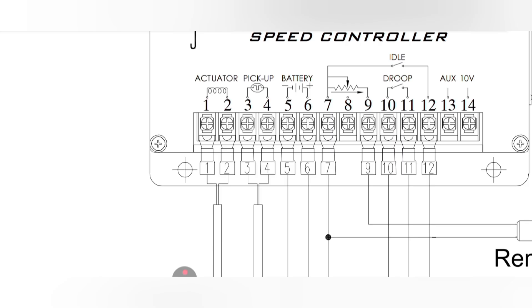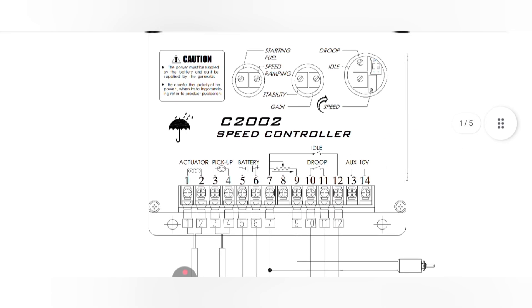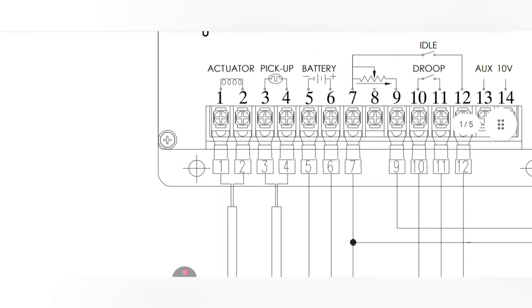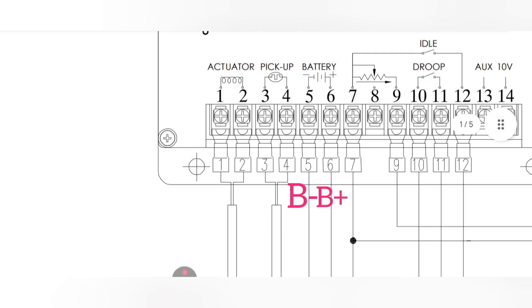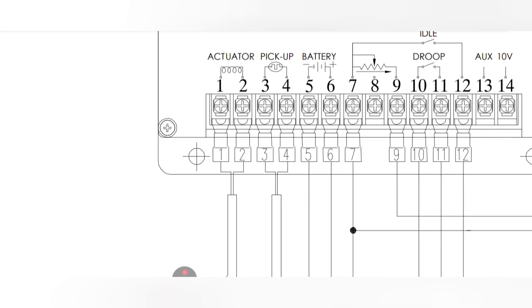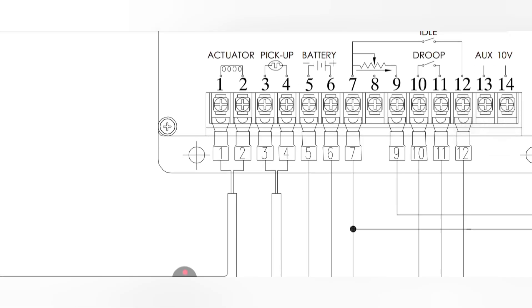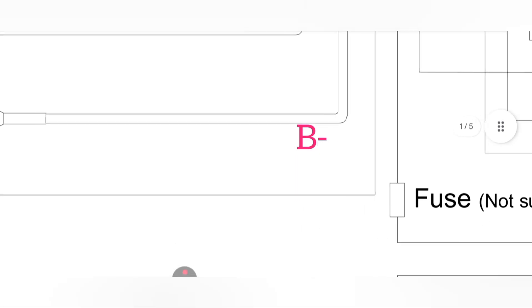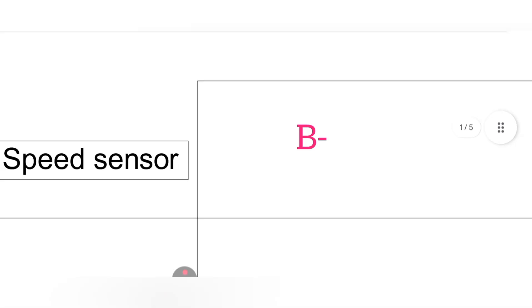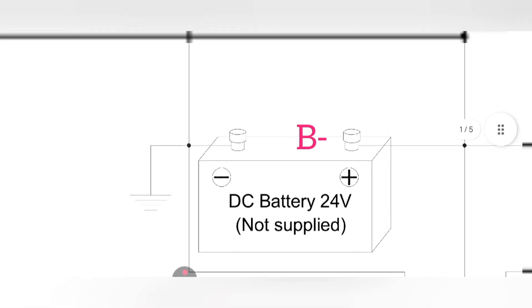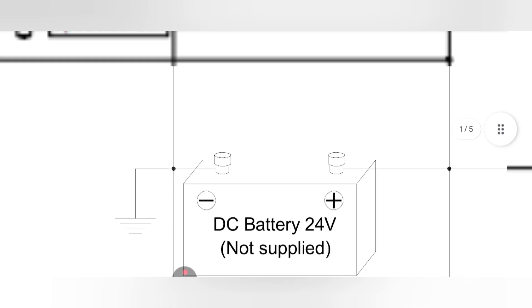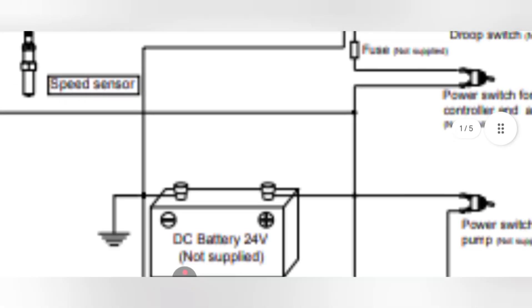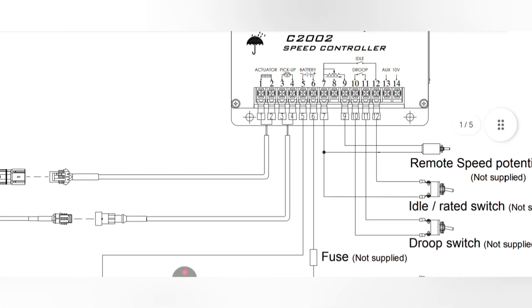Pin number five and six are the battery input to the controller. This controller requires an input supply of 8 volts to 32 volts DC. Pin number five is the battery negative input and pin number six is the battery positive input. Following the pin five wire, it goes to the 24-volt battery and connects to the battery negative, engine ground, and chassis ground.